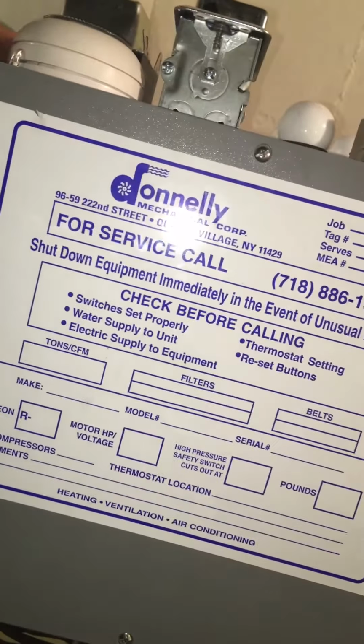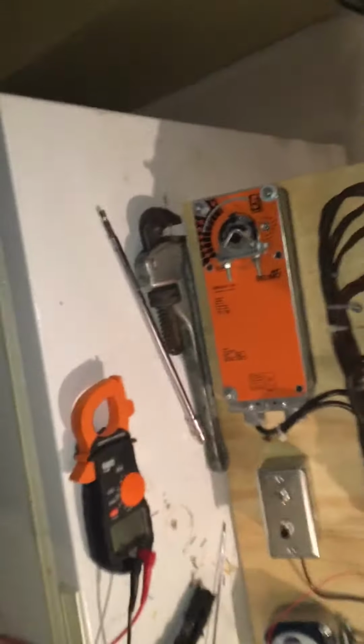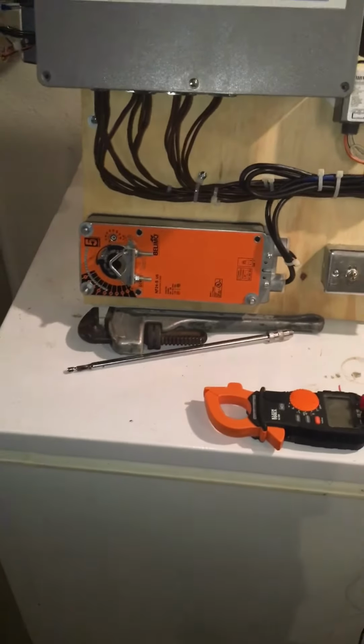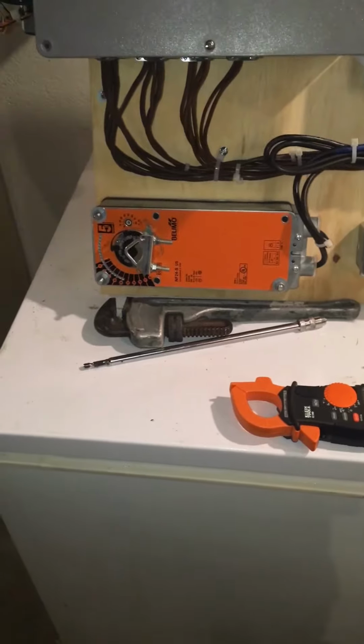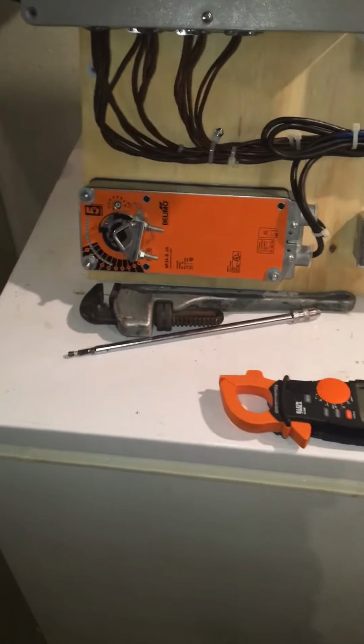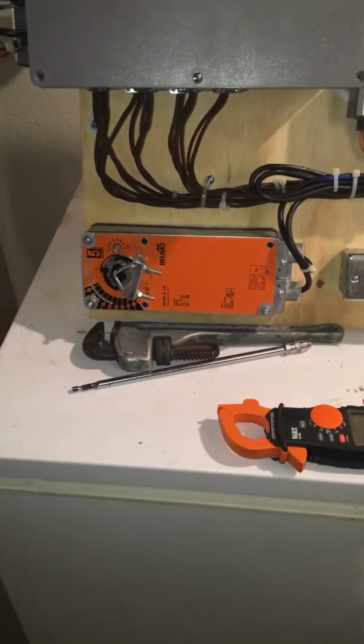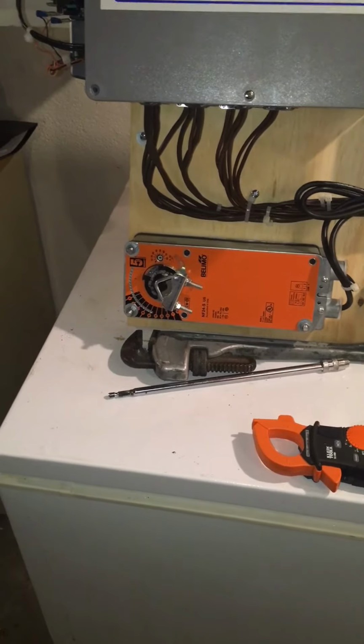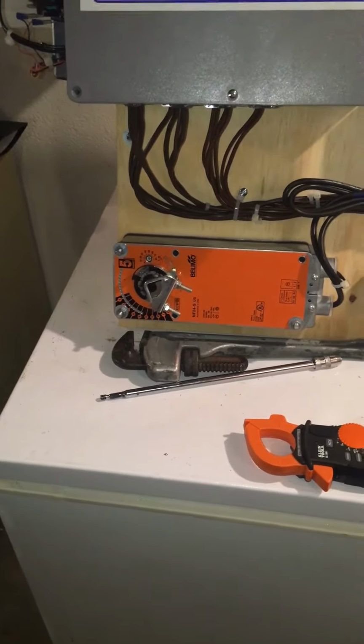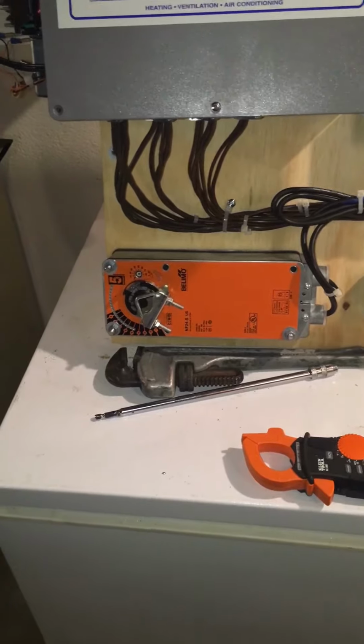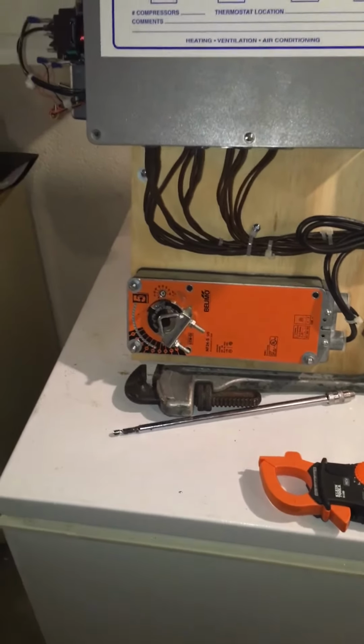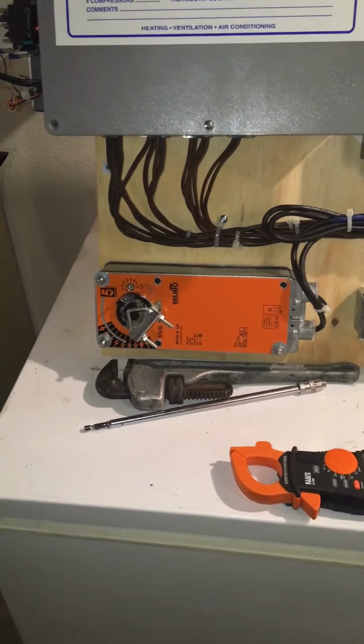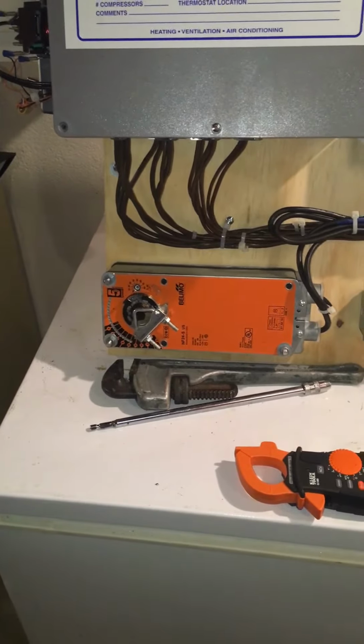So basically we start off with turning on the fan. That engages the Belimo motor. In the schematic I show, when the Belimo fully opens, we do two things. We make the indoor fan contactor turn on, and at the same time we energize the R1 relay, which is used to interlock the cooling circuit.